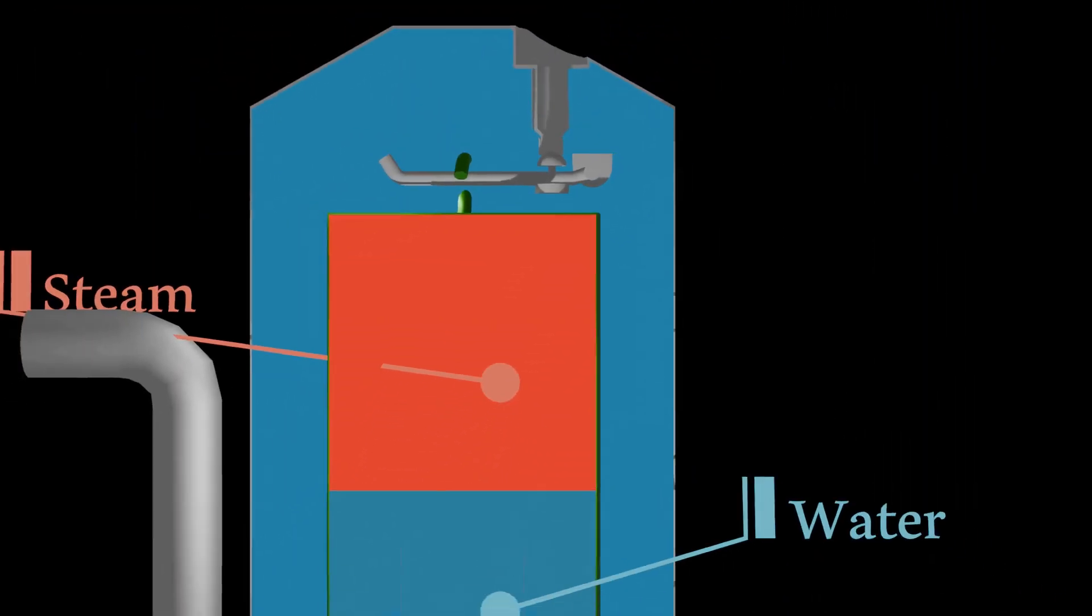As time passes, the steam loses its heat to the surrounding water. As a result, part of the steam condenses. When steam condenses, its volume decreases significantly and the bucket loses its buoyancy. So the valve starts to open. This will allow water to exit the trap.